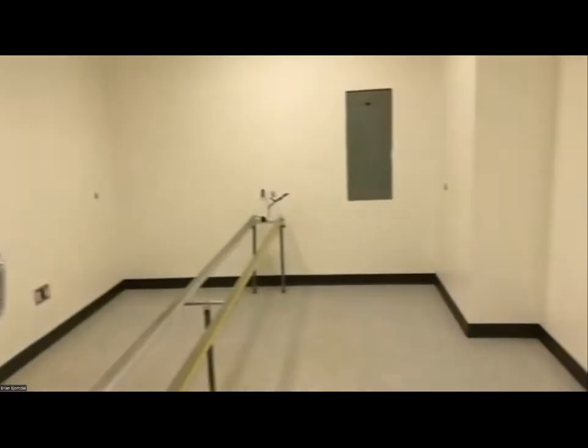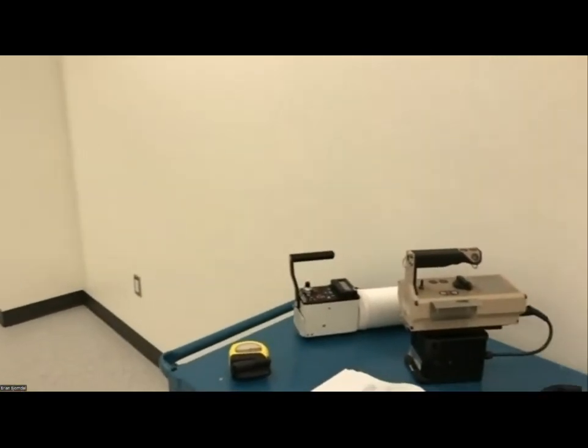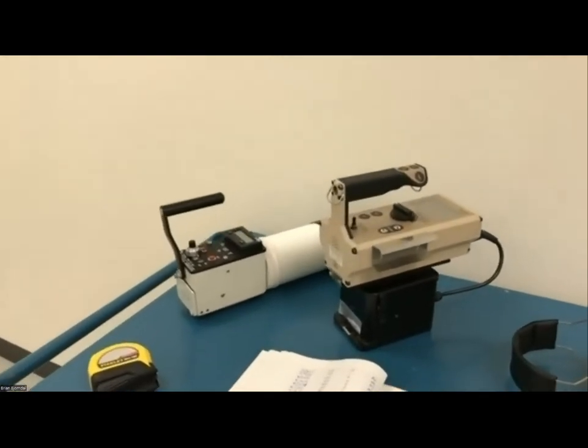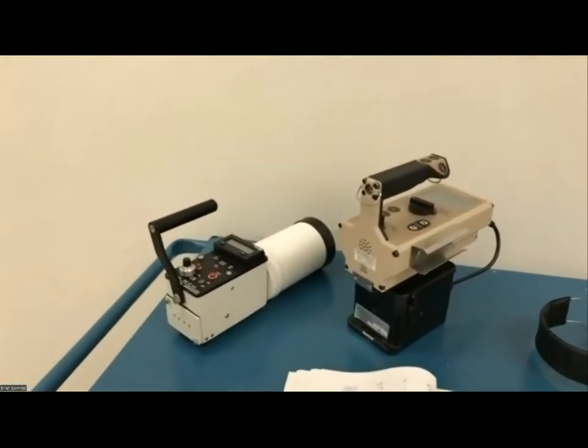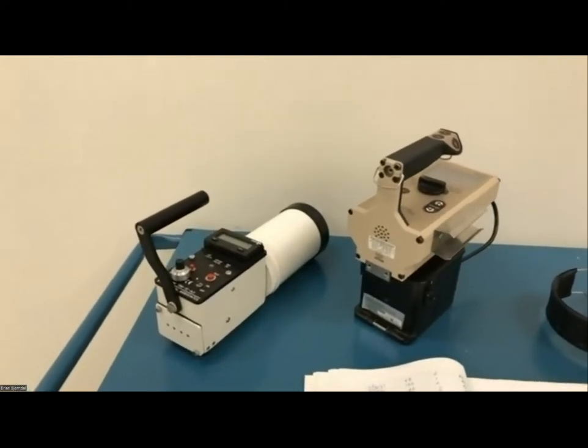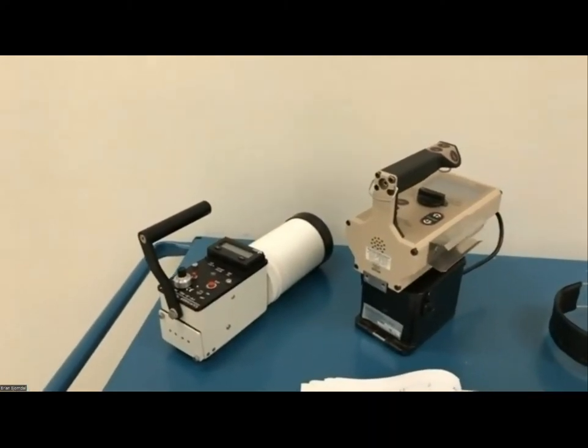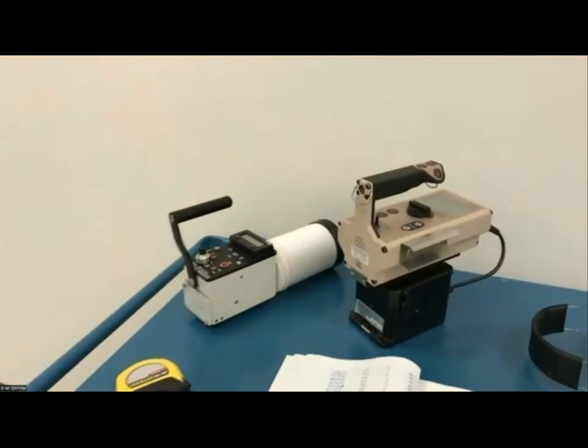So we have to make sure the instrument's positioned properly because the beam has a width and height. So we have to make sure that the detector is in that beam and that the separation between the source and the detector is at the proper distance to achieve the desired dose rate. So depending on the instrument, you saw some of these ones Tabby was showing you, we use a bunch of high-tech wood shims and things like that to shim it up to get it to the right dimension, right location. So that's not very high-tech, but it's very effective because it's only temporary. So we have a lot of little wood shims and things that we can use to get that detector at the right height so that it's right in the beam of the instrument calibrator.